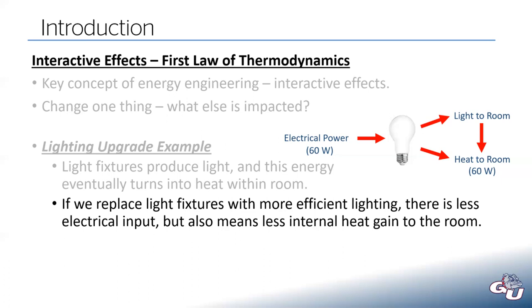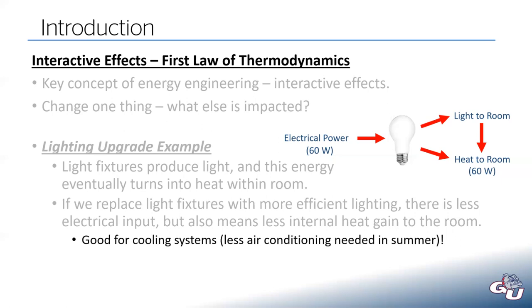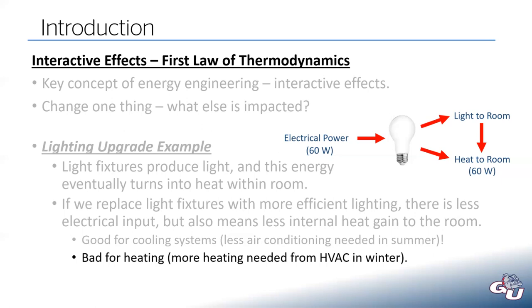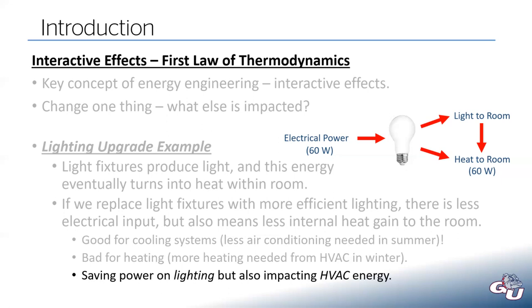So what this means is if we put in more efficient lighting and we reduce the heat off of those light fixtures, this is a good thing for our cooling systems. So in the summer months, now our air conditioner doesn't have to work as hard because these lights are not putting out as much heat as they used to. But it's bad for our heating systems. So now whatever heating you have, again, in the room you are sitting in right now, you probably have some electric baseboard heat or maybe a gas furnace somewhere. If the light is producing less heat, now your heating system has to produce more heat to make up the difference. So if we're going to save power on the lighting system, we are also impacting the HVAC energy.